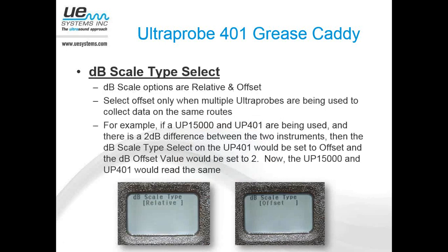Okay, the next one is going to be of use to you if you have multiple Ultraprobes in use. I'll give you an example here, but it's the dB scale type select. Your 2 choices are relative and offset. And again, this will only be used when you've got multiple Ultraprobes being used to collect data on the same routes. So the example we have here is if you have an Ultraprobe 15,000 and you're using the Ultraprobe 401, you may get different decibel level readings between the 2 instruments.